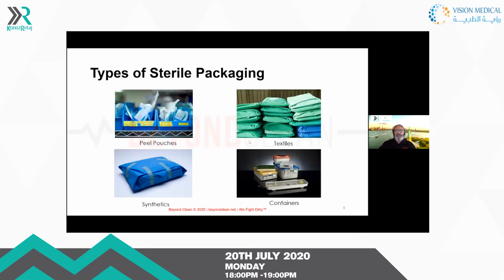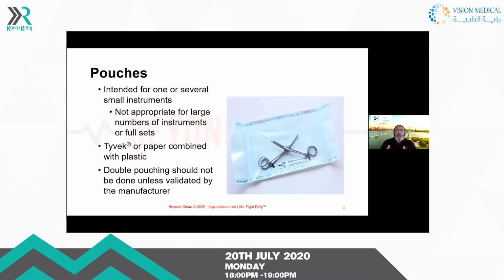Again, these are the types of packaging we look at. And as I stated, textiles we do not use much here in the United States anymore, and I assume for you as well. When we talk about peel pouches, we know that they're intended for small instruments, not appropriate for a large number of instruments as you package them. They can be Tyvek or paper and plastic combined. And we always want to make sure that we're only double peel packing if the manufacturer says it's okay to double peel pack. Some still say it is only okay to single peel pack. So please make sure that you check the manufacturer's instructions for use as you're using this product.